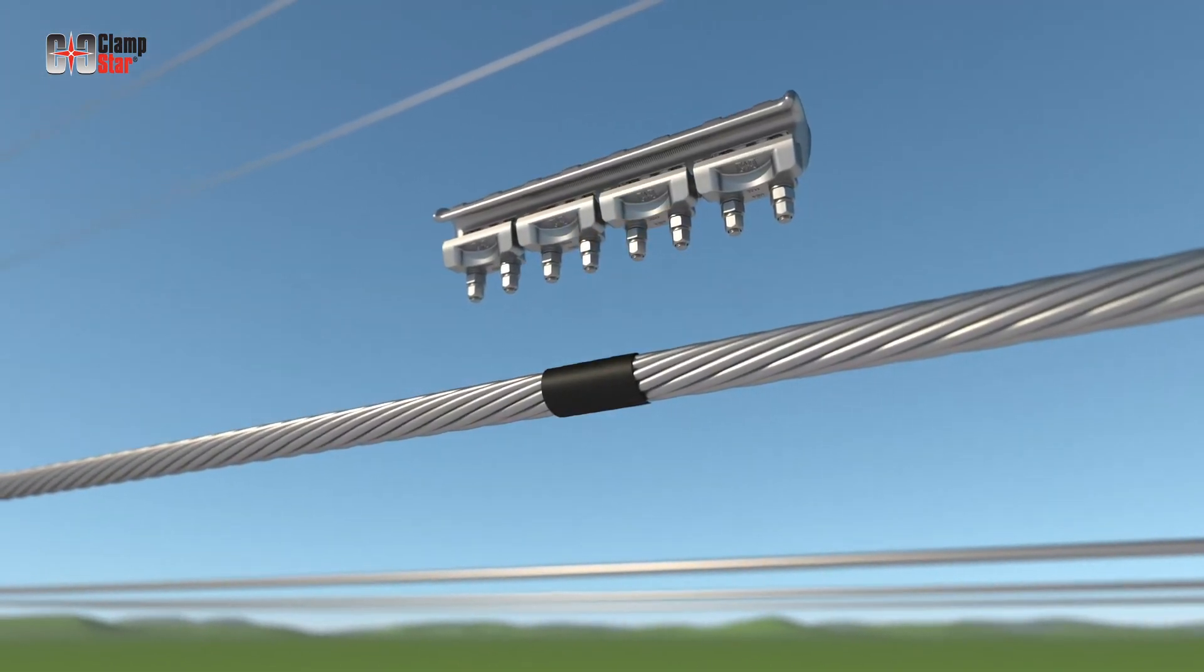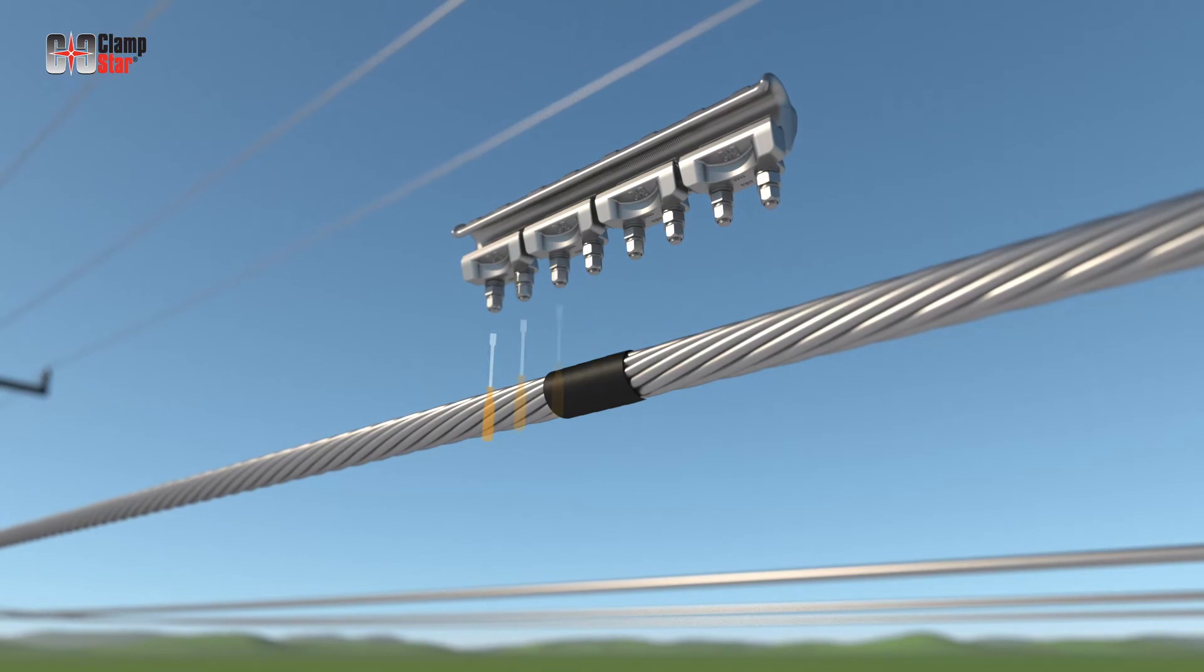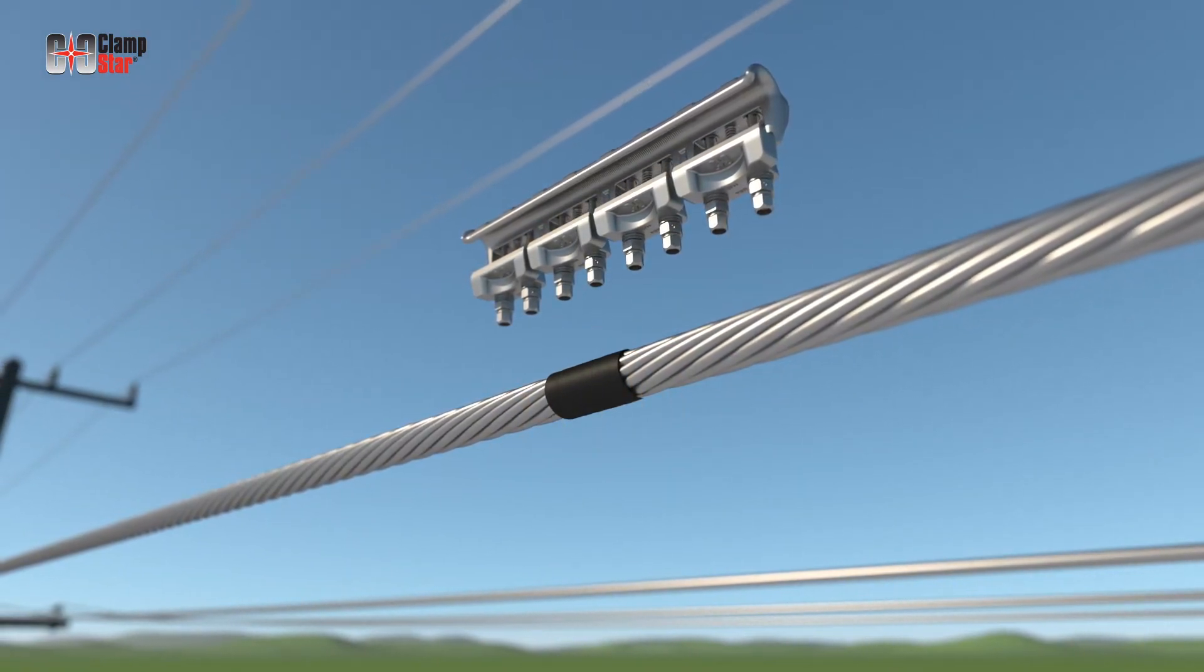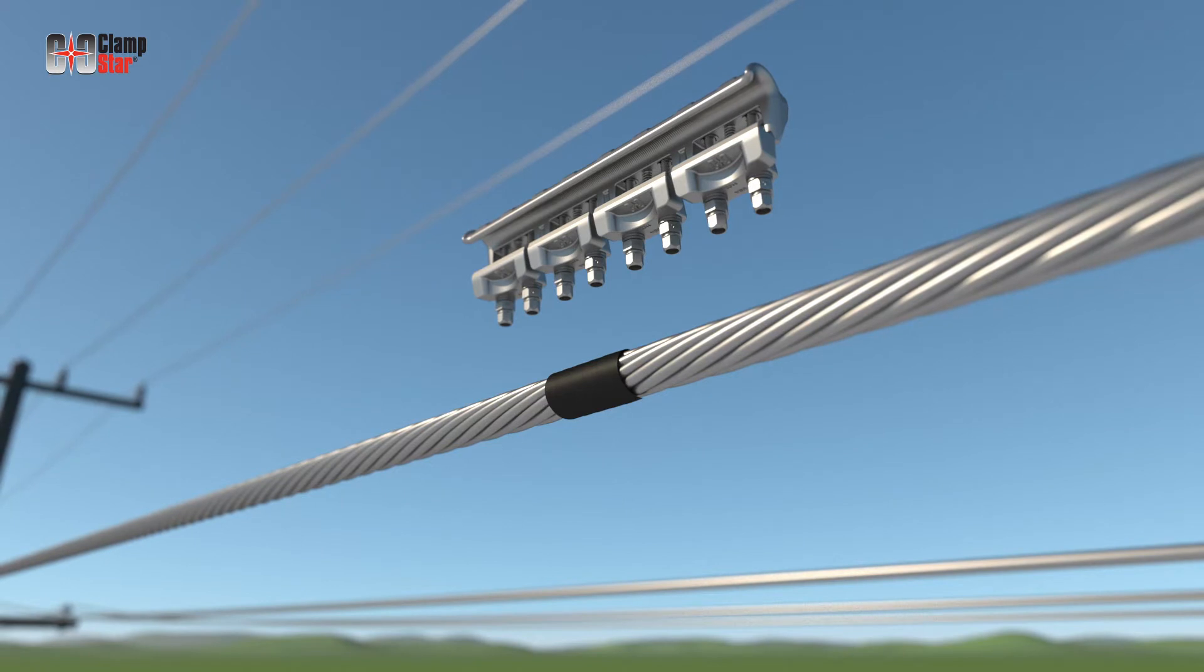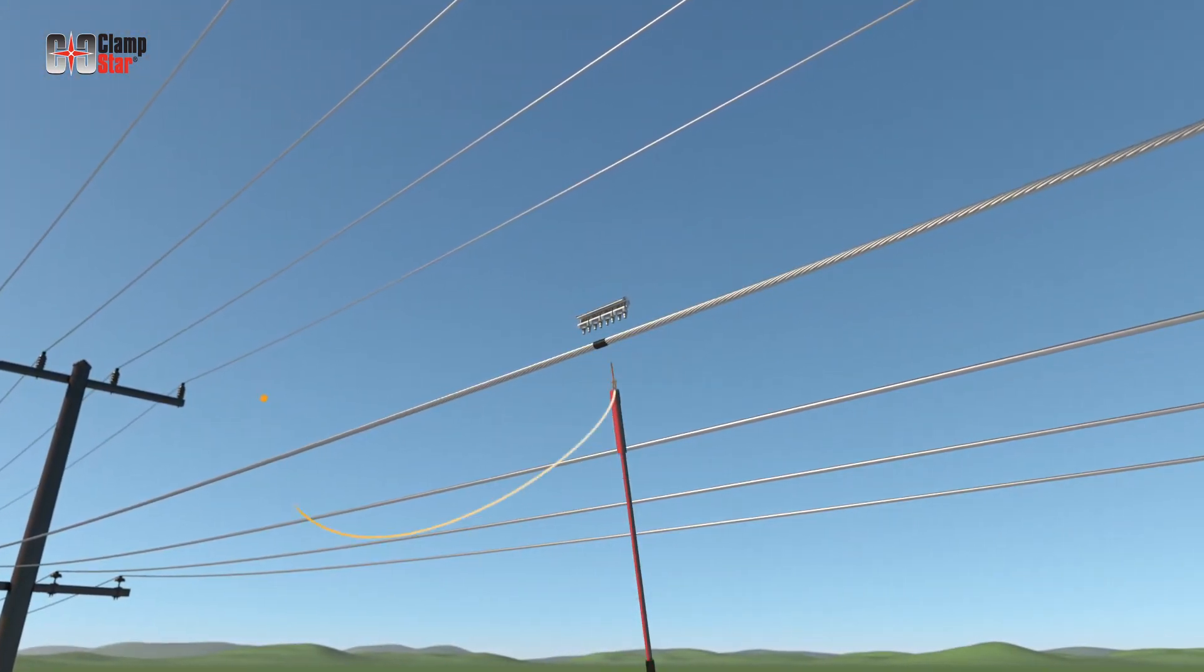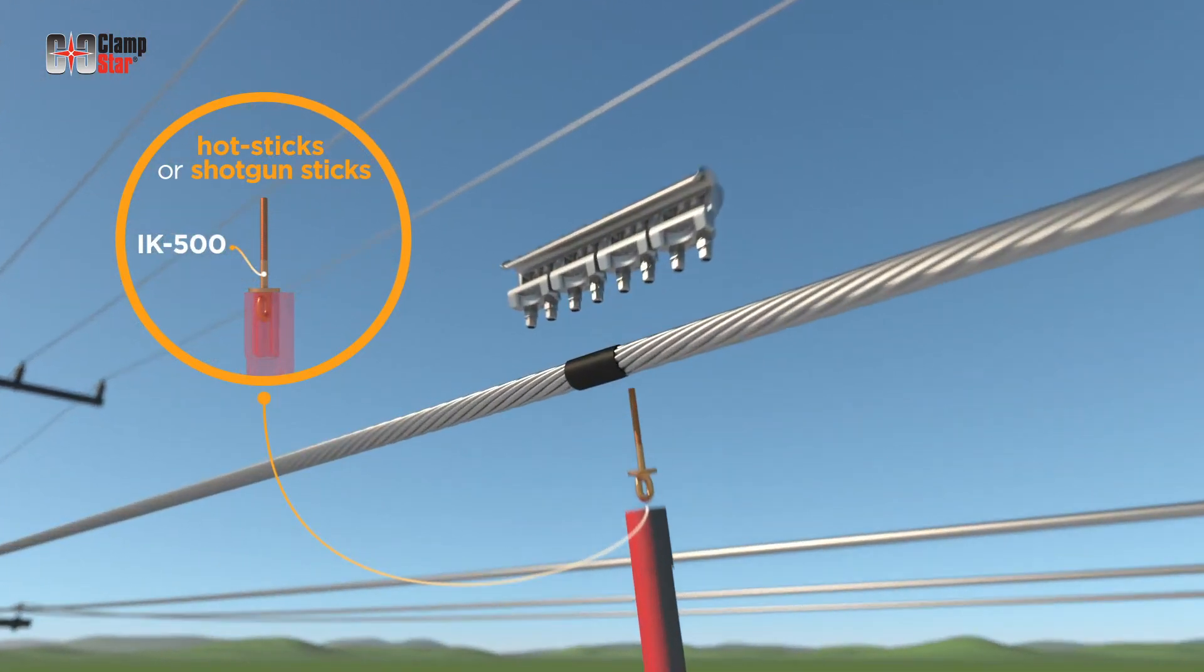Before placing the CRU unit on the conductor, loosening the nuts may be necessary to ensure the keepers are opened wide enough to accept the conductor. In addition to glove installation, ClampStar units are designed to be installed with hot sticks or shotgun sticks.